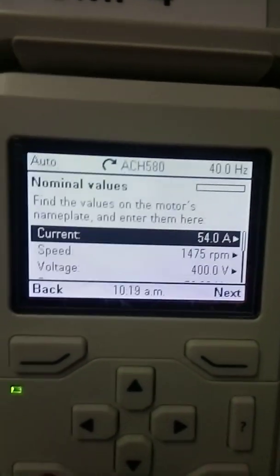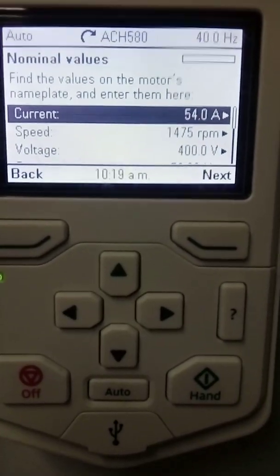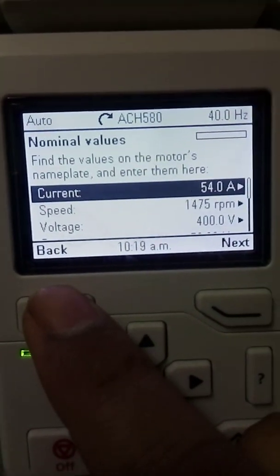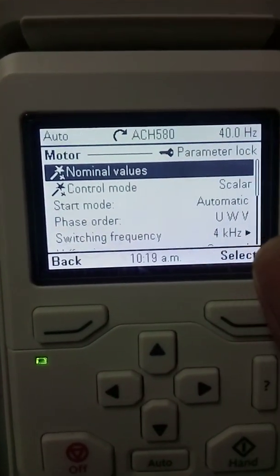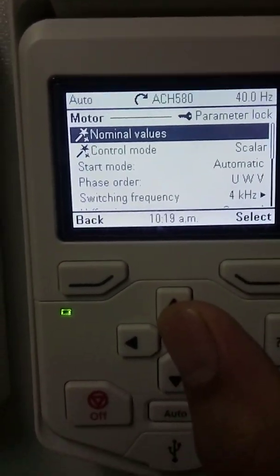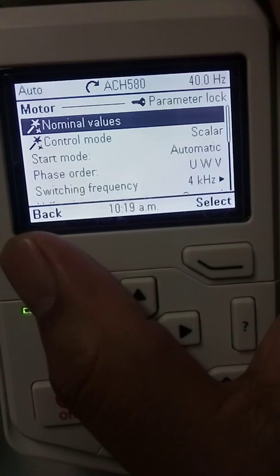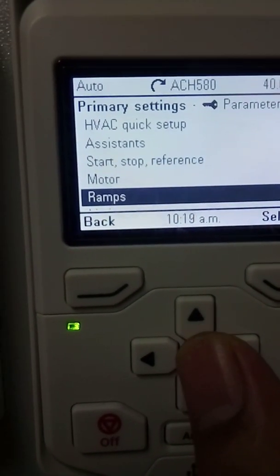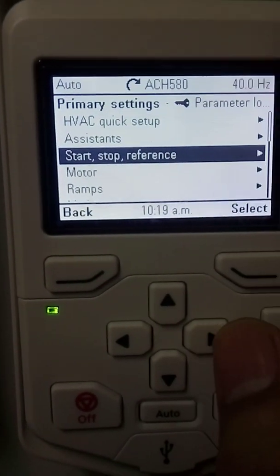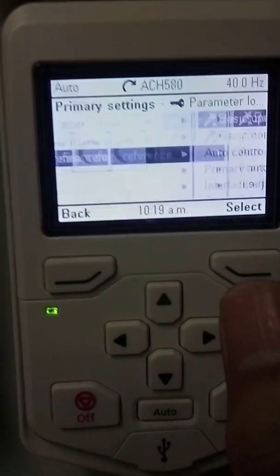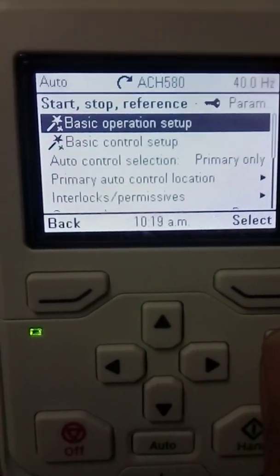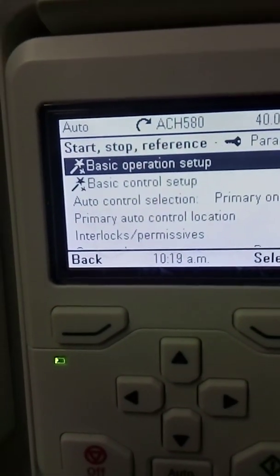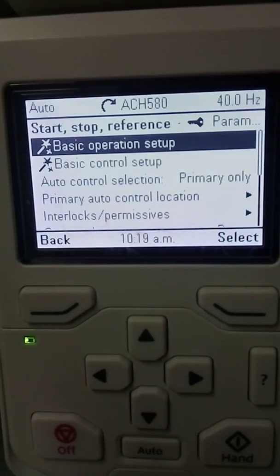So those were the values you have to put in the VFD. Next I will show you some other configuration needed to run your motor. You have to go to the start/stop reference. Select your start/stop reference — it will ask if you would like the basic operation setup, basic control setup, auto control selection, primary only, or primary auto control.